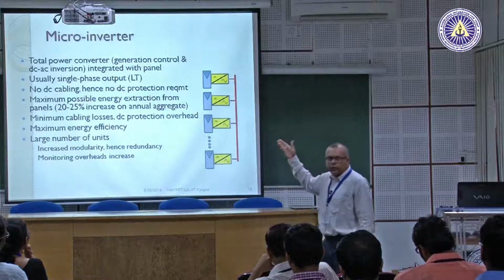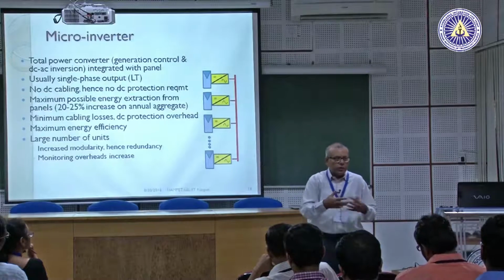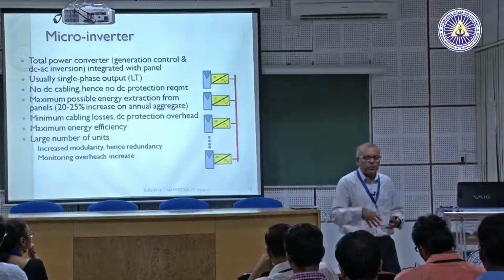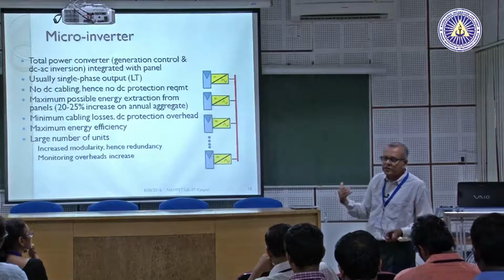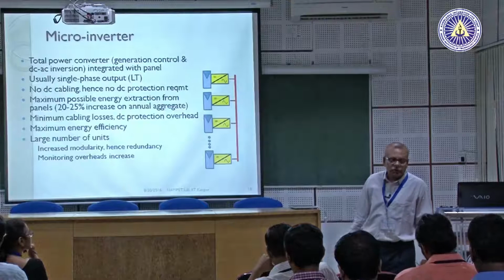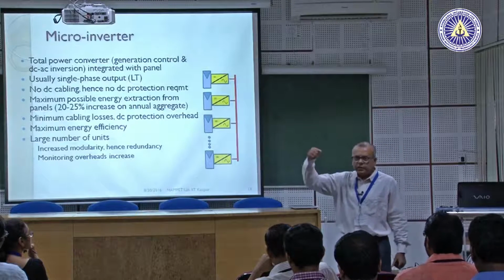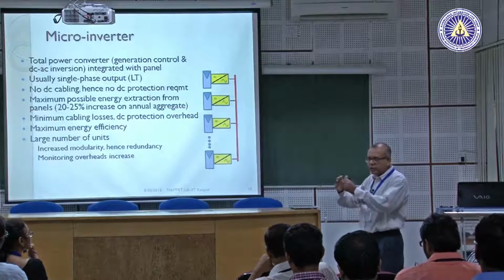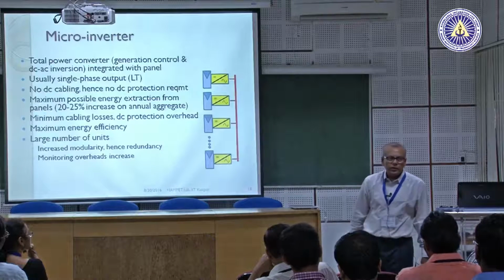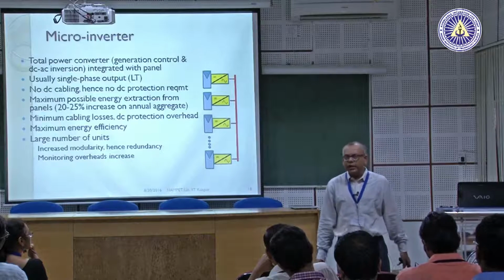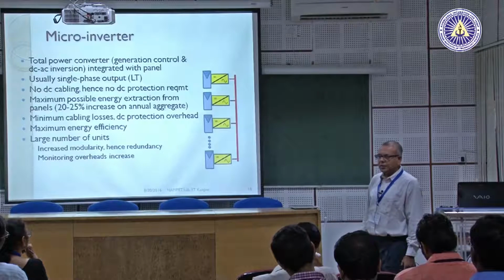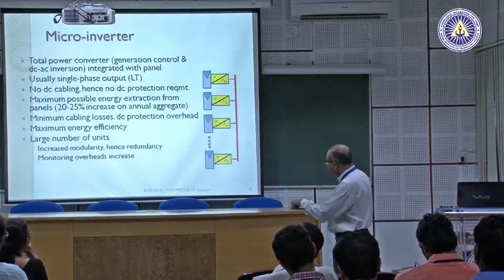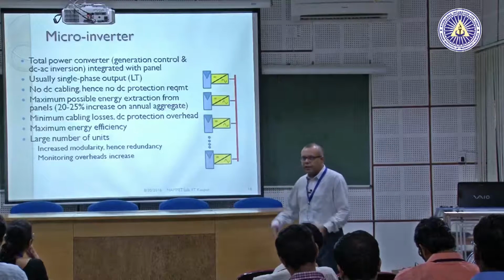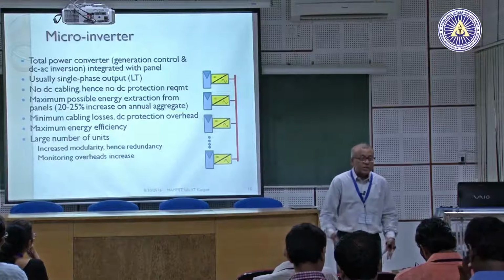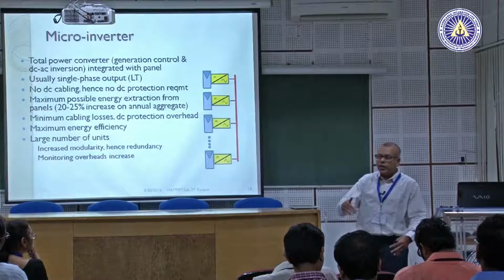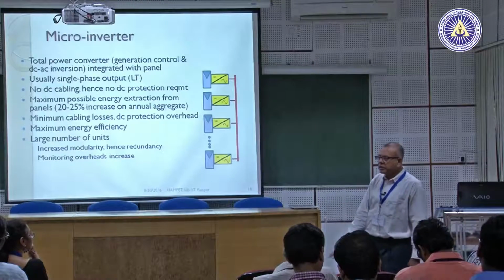The worst part of protection—switchgear and protection like breakers and switches in DC—is that we don't have a zero. So if there's a current arc when you open a contact, it doesn't naturally die down, which it does in AC. So having switchgear and protection in DC circuits, especially when voltage is on the higher side, is always a challenge and a nightmare.